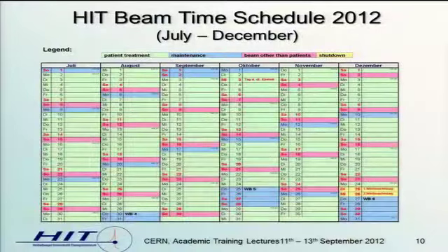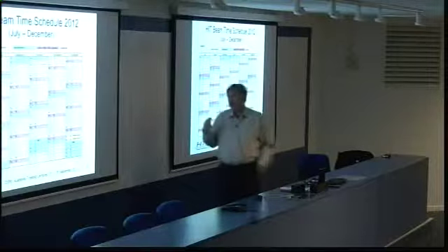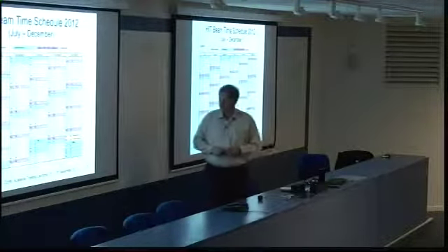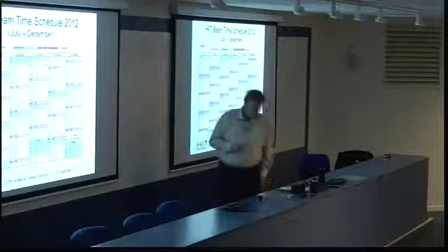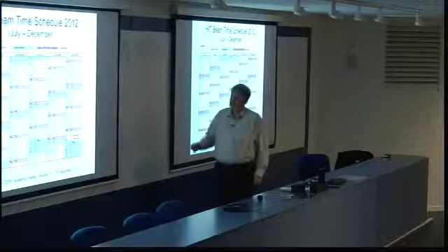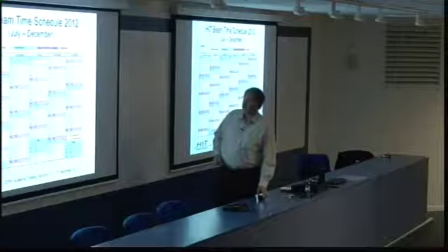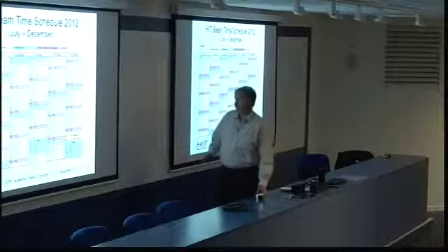So what you can see here is our beam time schedule in the second half of 2012. We are around here, so the machine is running and irradiating patients. Most of the time is dedicated to patient treatment, normally Monday to Saturday. Sometimes every 2-3 weeks we have a short maintenance interruption on Mondays, a half Monday. The rest is dedicated to other things. This is just to have the possibility to react to short problems, and as we are still commissioning the gantry, a lot of installations are done on these Mondays. So we think that next year we can reduce these maintenance Mondays from every 2 to every 3-4 weeks.